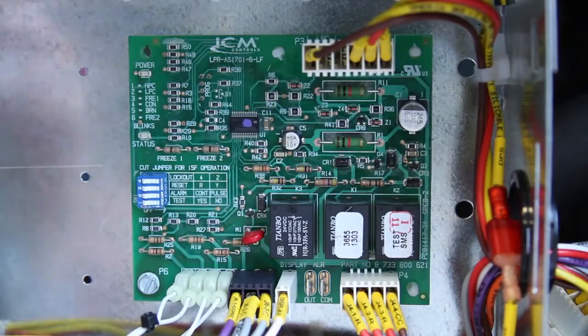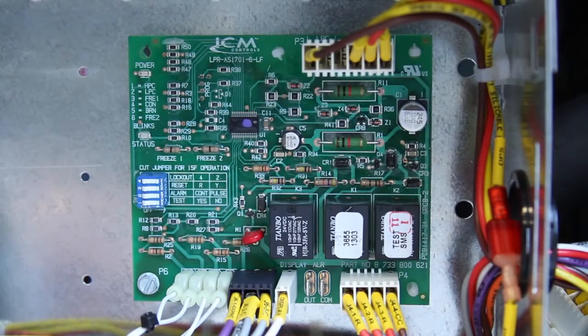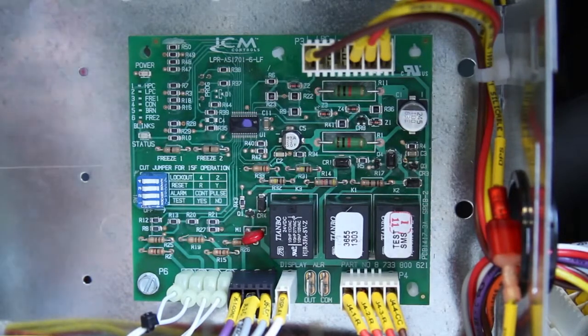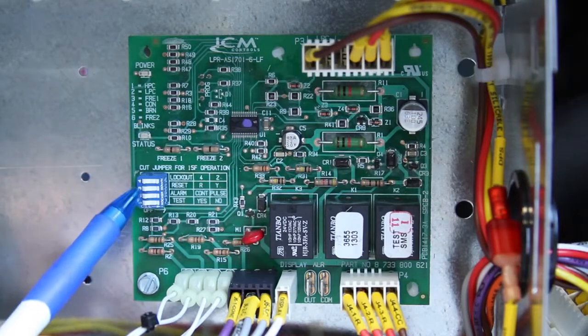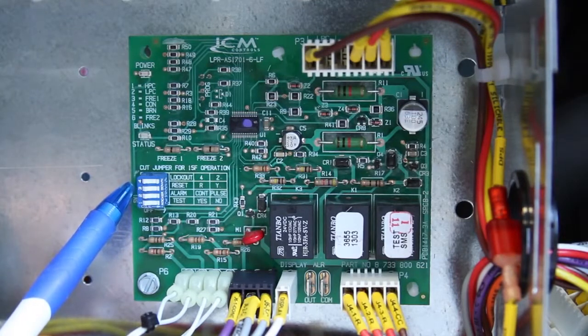Then once a unit goes into a hard lockout, it can be taken out of lockout by resetting the thermostat. You can also set dip switch number 2 so that it takes a 24-volt power reset in order to bring it out of a hard lockout. So you have the ability to adjust this slightly using dip switches 3 and 4.